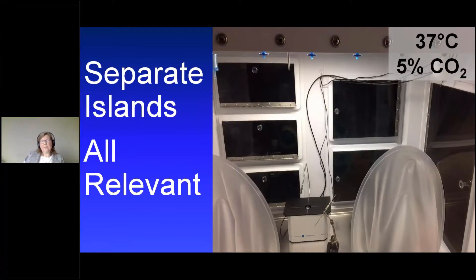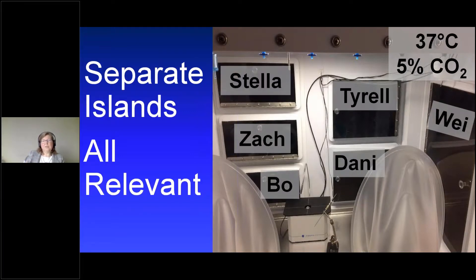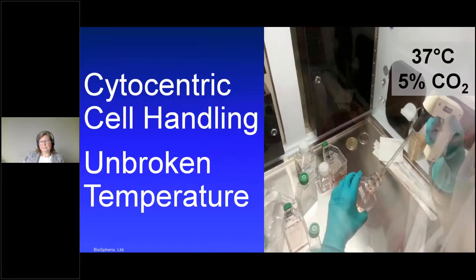With compartmentalization of the cell culture environment in the ex vivo system, you can have multiple parallel environments — separate islands with separate relevant conditions for your model. In my lab I set up an ex vivo with six different oxygen levels simultaneously to do range-finding experiments. Cells never have to suffer variable conditions because I can set the cell processing chamber to match any one of these incubators before I open the door — the cells never know they're out of the incubator. In your lab you could also use this to separate users, so nobody interrupts anyone else's experiments by opening a door and creating variable conditions. Separate islands, all relevant.